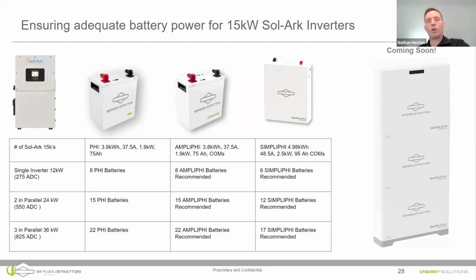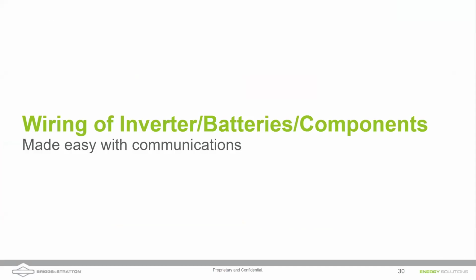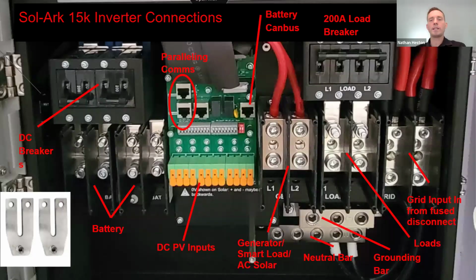If you're looking for a smaller, less expensive system, you can always install a smaller system like a Sol-Ark 8K or a Briggs & Stratton 6 kilowatt and just back up part of the home. Yeah, or a load shedding device like we saw with that Span panel as well. Exactly. So that's the other thing you can do: if you have a load shedding device, you can reduce your loads by having some of those loads shed under high demand times. And so that's one of the values of having a smart loads panel like that Span.